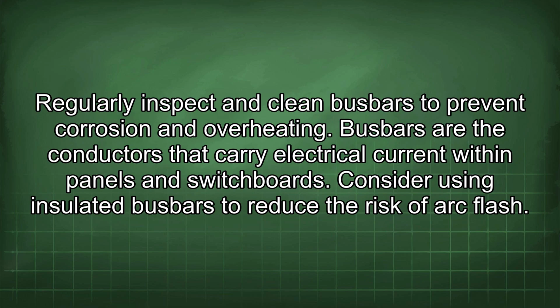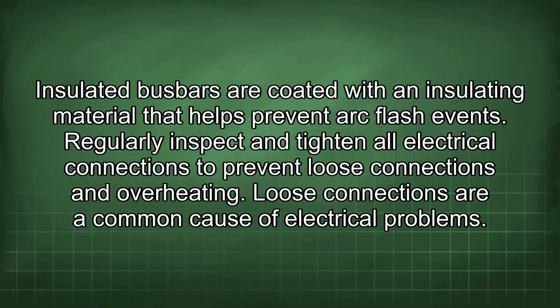Regularly inspect and clean busbars to prevent corrosion and overheating. Busbars are the conductors that carry electrical current within panels and switchboards. Consider using insulated busbars to reduce the risk of arc flash. Insulated busbars are coated with an insulating material that helps prevent arc flash events. Regularly inspect and tighten all electrical connections to prevent loose connections and overheating. Loose connections are a common cause of electrical problems.